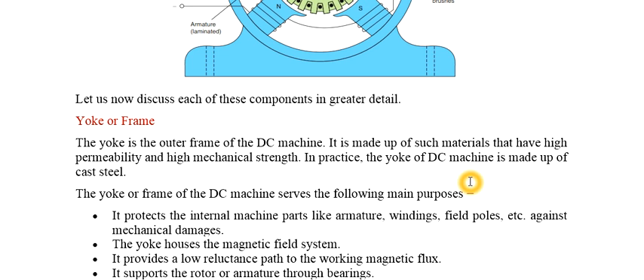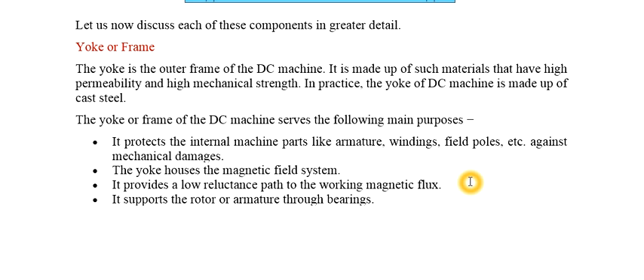The yoke is the outer frame of the DC machine, generally made of cast steel, which has high permeability and provides mechanical strength. Its purpose is to provide protection, keep the magnetic field system in place, and provide a low reluctance path to the working magnetic flux — similar to how a transformer's magnetic core provides a path for flux. It also supports the rotor or armature through bearings.